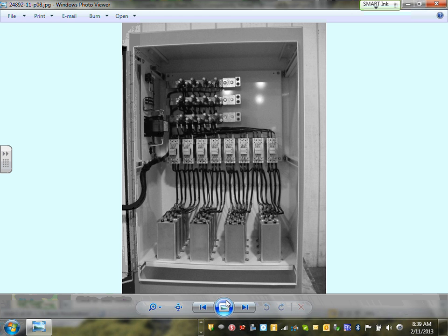There's my friend. You monitor the power factor. When the power factor goes below a certain value, close a set of contacts to put a bunch of capacitors on. And then the power factor keeps going down again. Another set of contactors closes and puts this set of capacitors on. And then the second, and then the third, and then the fourth. That's how they control how many caps you can put in your system. Either you put them all in at the same time or put them in steps.